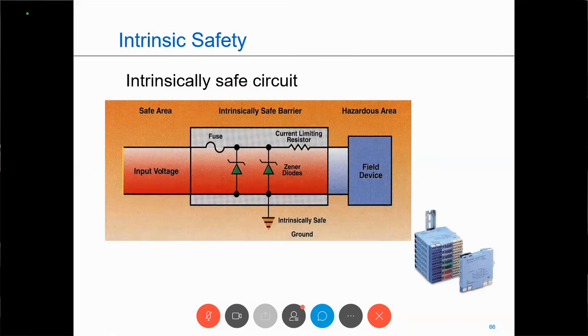So what I'm going to have is an intrinsically safe circuit that will contain a barrier. And this particular barrier is going to bleed the excess voltage off through ground through the Zener diodes, and it's also going to have a resistor to keep the current where it belongs. Also, there's isolation barriers, which are also called line conditioning barriers. This particular unit that we're showing here is called a Zener barrier. So there are some different types of barriers that can be used in intrinsically safe.